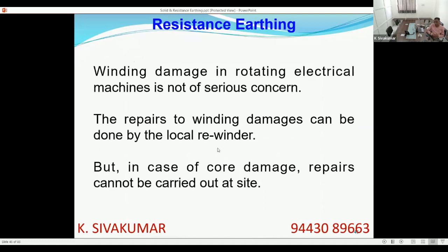Now, why should you worry about core damage? If you recall, winding damage, suppose your winding insulation burns or winding gets damaged, in big cities, at least even including tier 2 towns, you will have a good rewinder, or a rewinder authorized by the equipment manufacturer, motor manufacturer, generator manufacturer, available in a nearby town or city. So you can always take the damaged machine to him and he will be able to rewind it and give it to you. The machine can be brought back to service very quickly if it is a winding damage.